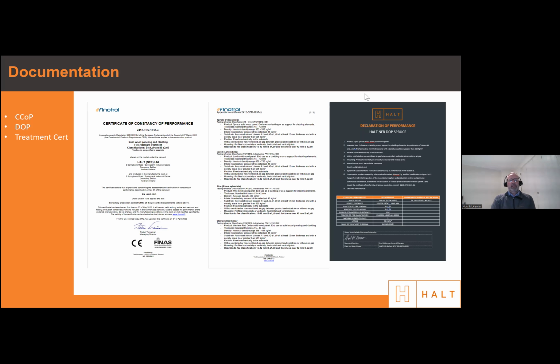Just a little on documentation. From an end user point of view, I went into detail earlier about field of application testing. When we're talking about products used in construction, end users should always look for a DOP - the Declaration of Performance - for that product, showing the declared reaction to fire. If a manufacturing process has provided that reaction to fire result, the manufacturer should also have a CCOP issued to them. These two things are the backbone of the process used and the declared product used on the construction. The DOP is really the key critical part.